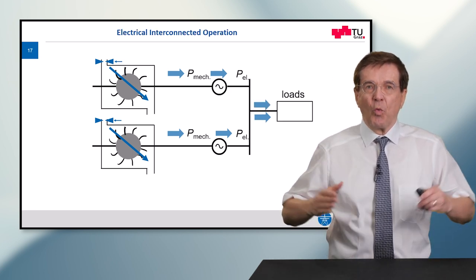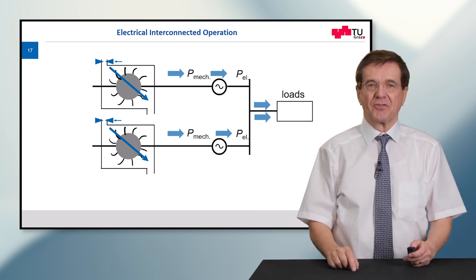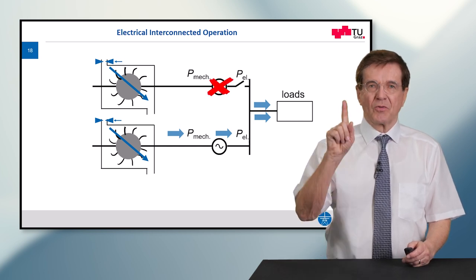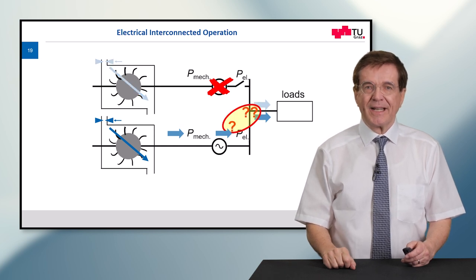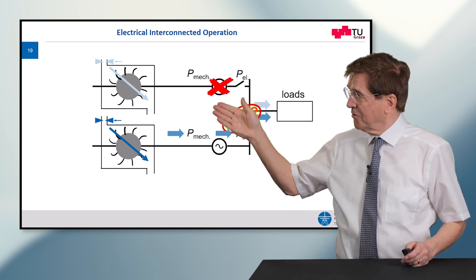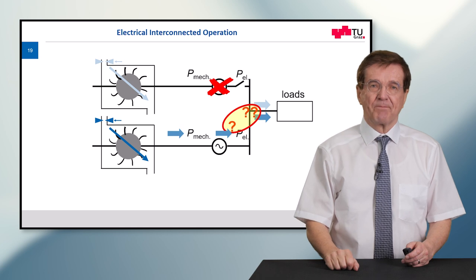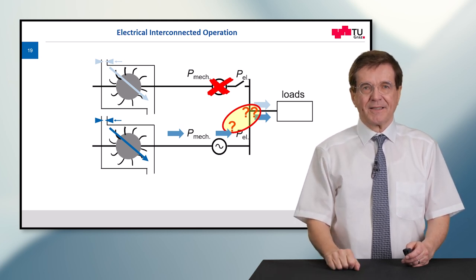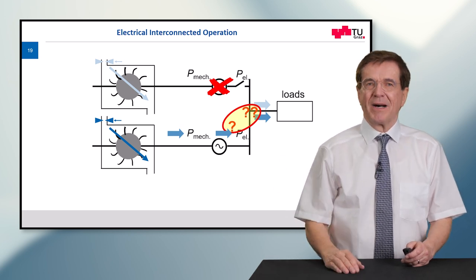Now let's assume something happens. For whatever reason, one turbine and one generator trips out, and now we have a severe problem. If you check this, the loads will take their old demand and power out of the grid, but there is only one generator supplying us. This is too little, so the imbalance of energy and the balance of power must be made up from something else.